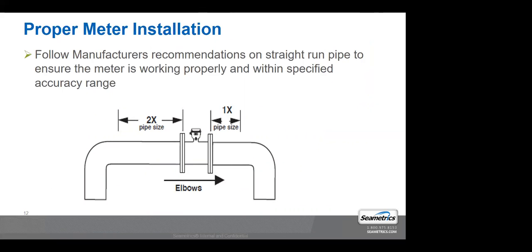Whenever you're installing a meter, it's critical that you look at the quick start guide or the manual and follow the proper installation guidelines. A lot of people will put a meter in line and then wonder why it's reading erratically. They think maybe it's recording more flow than it should be or less flow than it should be. Usually it's recording more flow if it's installed incorrectly. The reason it's important to install them correctly is because these meters are manufactured to a specified accuracy based on that installation.